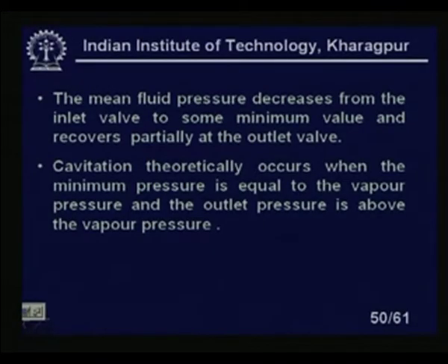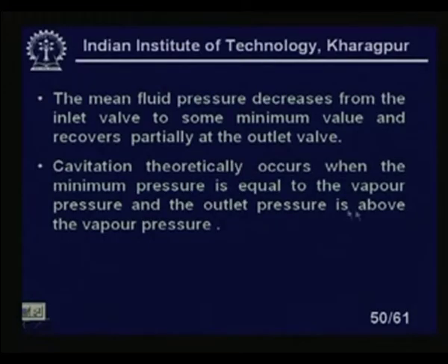Cavitation theoretically occurs when the minimum pressure is equal to the vapor pressure. It is very common in LPG industries, where the vapor pressure is a little less. So whenever this pressure falls, obviously cavitation will start, and the outlet pressure is above the vapor pressure. Then what will happen? The pressure will be recovered, and at that time the bubbles will collapse. So the cavitation will start.